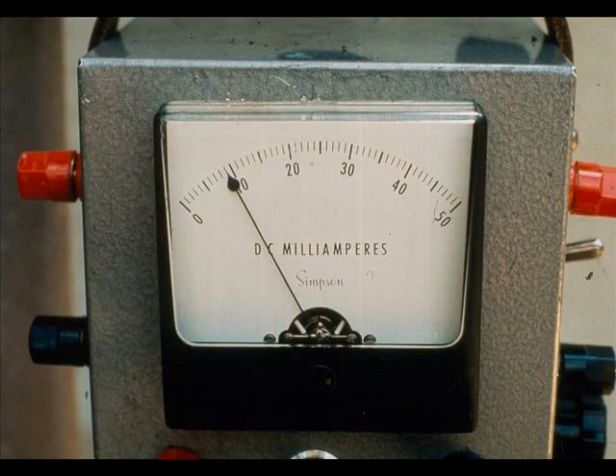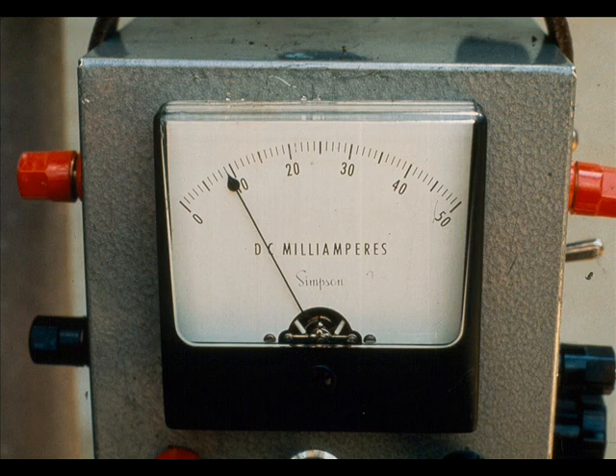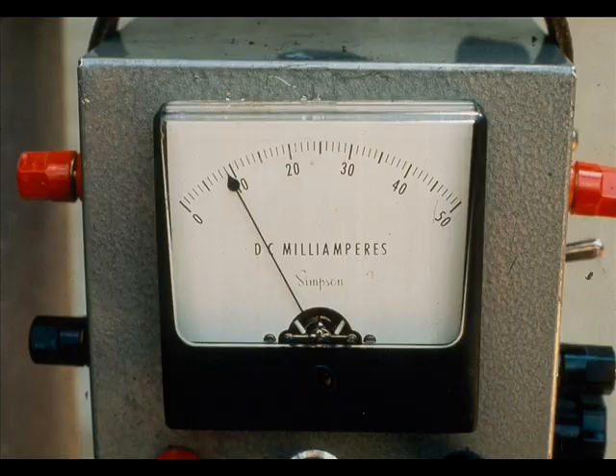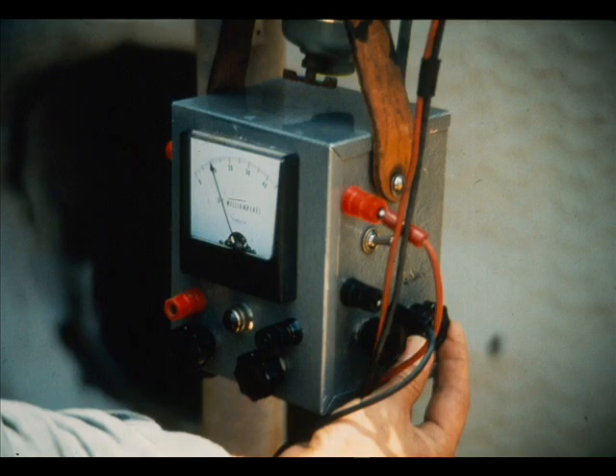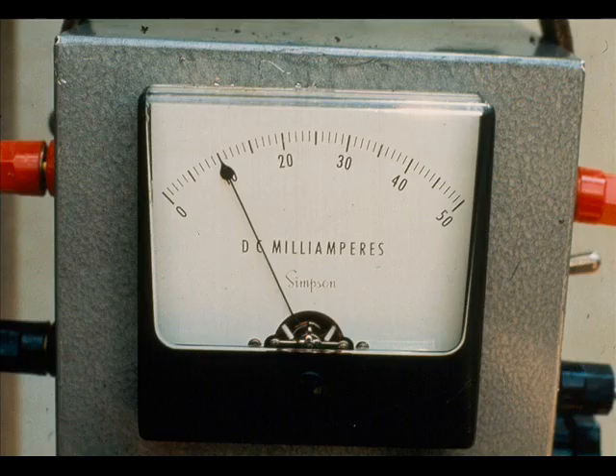Turn the coarse adjustment clockwise to where the meter reads near 10 milliamps. Trim the output with the fine adjustment until the meter reads exactly 10 milliamps.